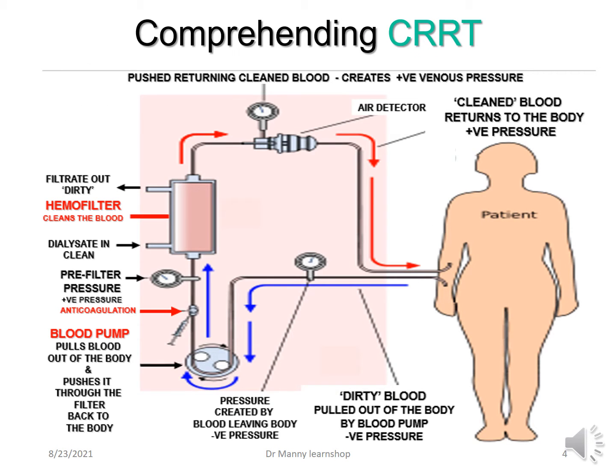When comprehending CRRT, we've got the patient. The patient typically has veno-venous access, which means blood comes out of a vein and returns into a vein. Unlike intermittent renal replacement therapy, which typically has a fistula or has access to an artery, pushes the blood out, and returns it to a vein. So, typically, the dirty blood, high in the waste product that you want to get rid of, or fluid, is pulled out of the body with a negative pressure. The pressure created by blood leaving the body is due to a negative pressure which can be recorded.